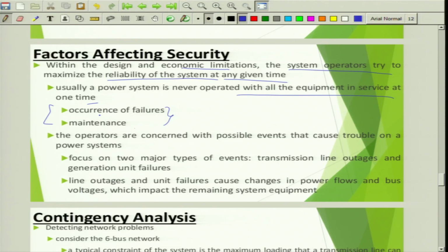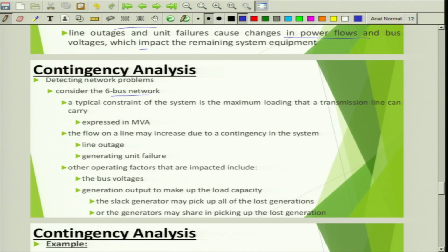So the operators are concerned with possible events that cause trouble on a power system. There are two types of critical events that are expected. One is line outages and the other is generator unit failures, right. So line outages and unit failures cause changes in power flows and bus voltages which impact the remaining system equipment. So consider the 6 bus network. A typical constraint of the system is the maximum loading that a transmission line can carry. This is expressed in MVA, right. The flow on a line may increase due to a contingency in the system, which may be due to a line outage or generator unit failure. Other operating factors that are impacted include the bus voltage and the generator output to make up the load capacity.